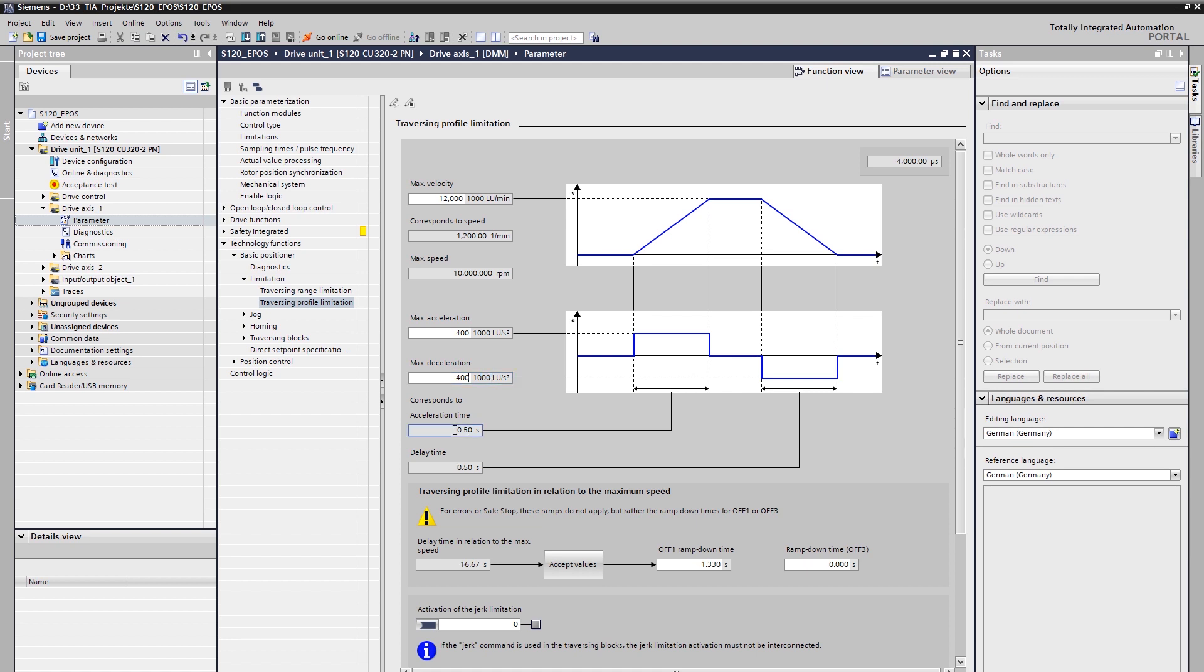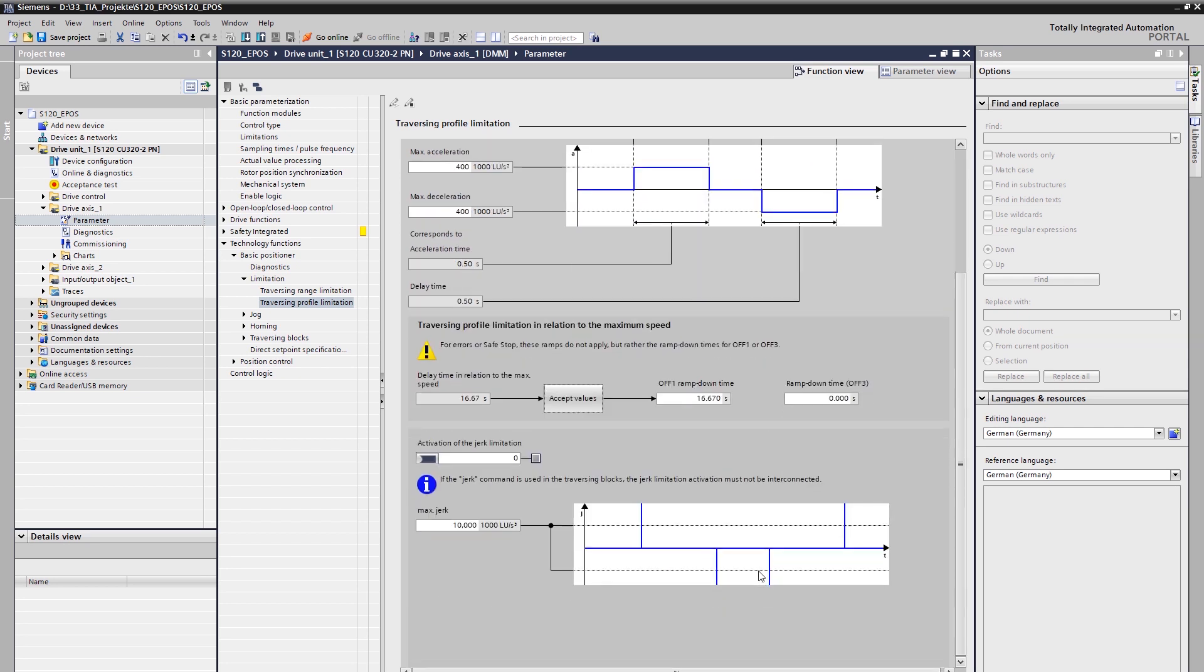The input for maximum acceleration and deceleration is done in 1000 LU per square second. As a note for parameterization, it should be considered that the deceleration times for OFF1 and OFF3 apply in the event of an error or a safe stop. With the acceptance, the corresponding delay time of the travel profile can also be accepted for the OFF1 ramp downtime. Thus, the ramp downtime of OFF1 corresponds to the deceleration time of the travel profile. Optionally, the jerk limitation can also be activated. This limits the change in acceleration and enables smoother starting and braking during positioning. This is necessary for example for the transport of goods or the protection of the mechanics. In our case, this is not considered.